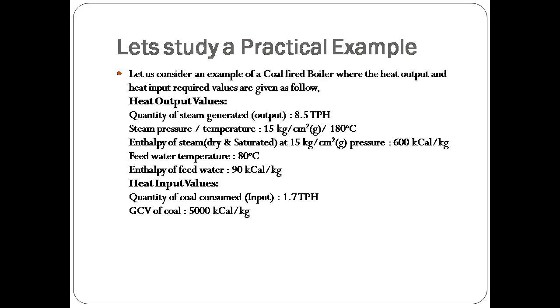Feed water temperature is 80 degrees centigrade, and by the chart you can get enthalpy of feed water, that is 90 kilocalories per kg. Heat input values: the quantity of coal consumed is 1.7 ton per hour, and the GCV, gross calorific value of coal, is 5000 kilocalories per kg. Now we apply the formula.